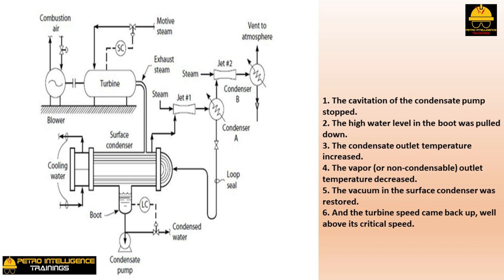The front-end plate on the cooling water side of the surface condenser — called the channel head cover — was removed. Most of the tube inlets in the channel head tube sheet were plugged with crayfish. The offending wildlife were removed, the condenser was reassembled, and motive steam was started to the turbine. Both the turbine and the air blower were running well above critical speed, and combustion air was lined up to the combustion chamber.